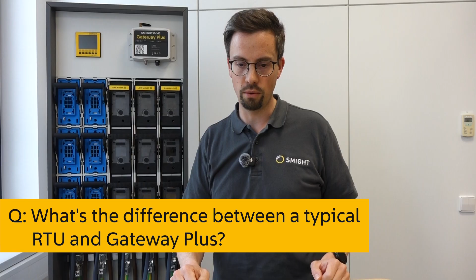Next question was, what's the difference between a typical RTU and the Gateway Plus? This was quite a perceptive question. An RTU stands for a remote terminal unit - this is the typical way such medium voltage devices would be connected to the control room. There are two differentiating factors. One is that RTUs can receive a signal and carry out actions, whereas our Gateway Plus can't - the direction of communication is different. Ours is one way, the data is coming out; with an RTU, data can come in and actions can take place. The other thing to consider is the level of complexity. What we're trying to implement is much simpler, but also much lower cost and easier to implement. Where you have these fault passage indicators, it may not be worth a full automation project to implement a full RTU system. We're saying you can bring those online in a much simpler fashion rather than going for a full RTU automation project.